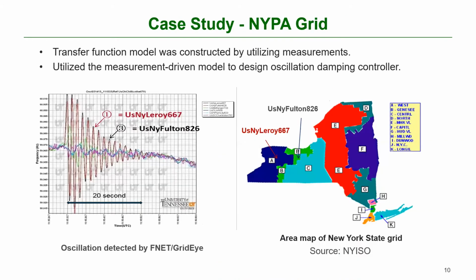Another one ongoing at a similar time is the New York system. We noticed that as you start to integrate more renewables in the New York area, you can start to see oscillations happening in the grid, and they are very interested in figuring out ways to damp the oscillations. Usually you can use FACTS devices, you can use generators to do the damping. You can use energy storage. You can use other means, but eventually I would see more preventive measures that can actuate the damping system for grid oscillations.